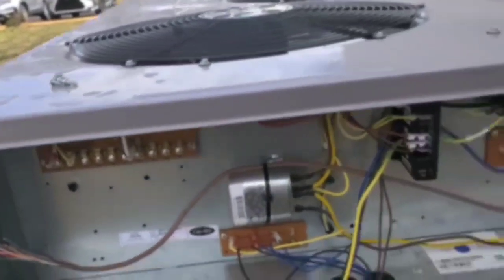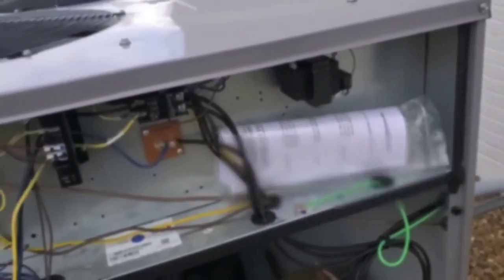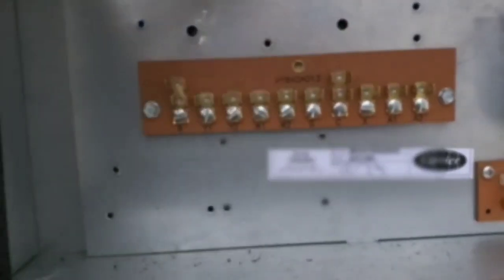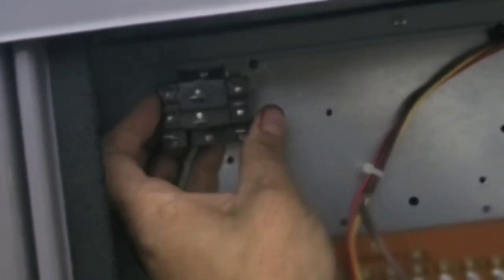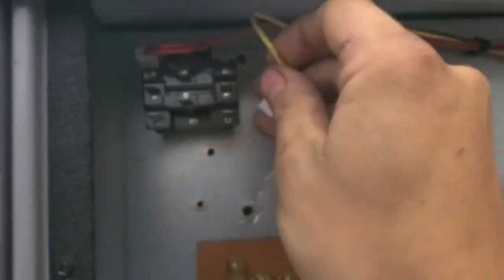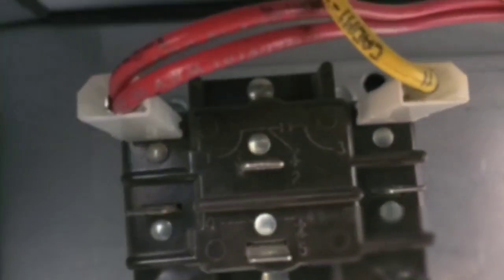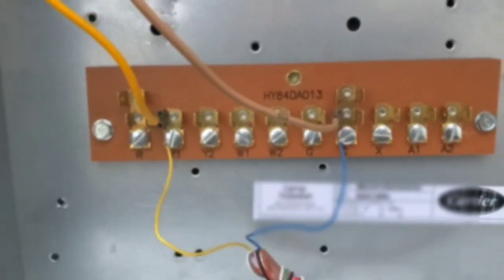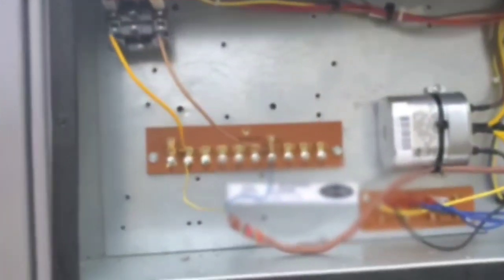But this isn't getting hooked to a normal commercial air handler. It's getting hooked to a twin set of furnaces. So this needs to turn into a normal, residential style condensing unit. We're gonna pull common, the red, and the yellow off the terminal block. We got ourselves a 24-volt relay. We're going to mount it right here, and we're going to hook our red and our yellow to it. Oh, it's normally open contacts, you see? Yeah, you see there? Normally open contacts. What's common? Just going to tie it up here out of the way. Pretend like it don't exist. Then from the coil of that relay, run to the C and Y1 terminals on the terminal block. That's it. Now it's just a condensing unit like every other.